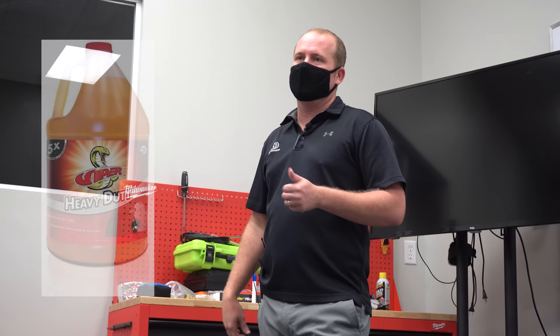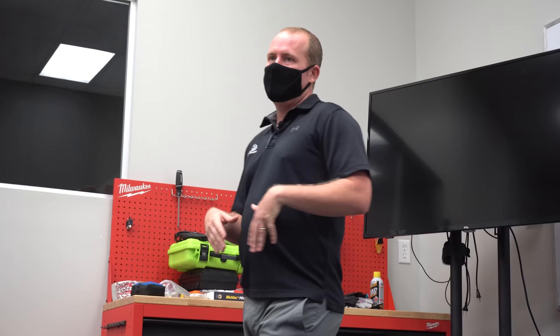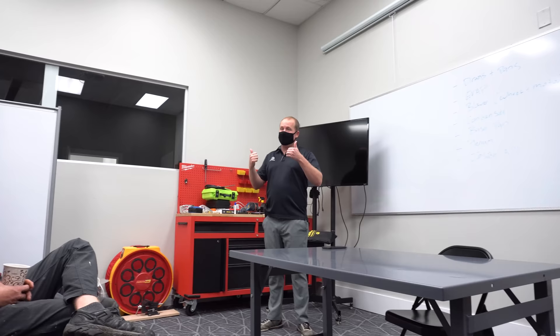What I'd prefer you do, generally speaking, is take some standard condenser coil cleaner — your Viper cleaner, that sort of thing — that is not super toxic and caustic, pour it in the drain line, and just let it sit while you're doing other things. Let it work and soften the buildup. It's not going to be as exciting as Drain Solve, but it will break it up. Also — do not put Drain Solve in a drain pan. Don't do it, because it will react with the coil and everything else, and it's not good.